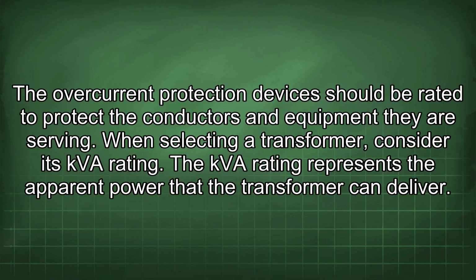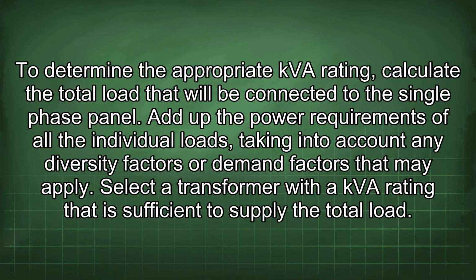When selecting a transformer, consider its kVA rating. The kVA rating represents the apparent power that the transformer can deliver. To determine the appropriate kVA rating, calculate the total load that will be connected to the single-phase panel. Add up the power requirements of all the individual loads, taking into account any diversity factors or demand factors that may apply. Select a transformer with a kVA rating that is sufficient to supply the total load.